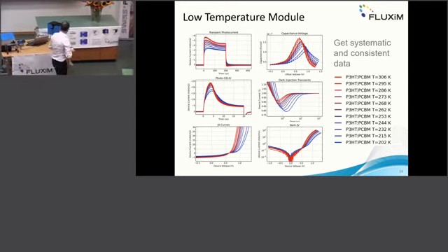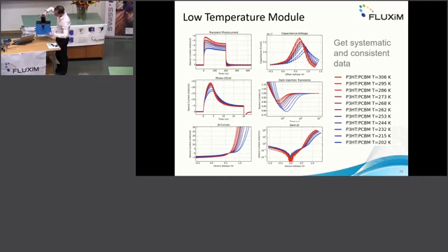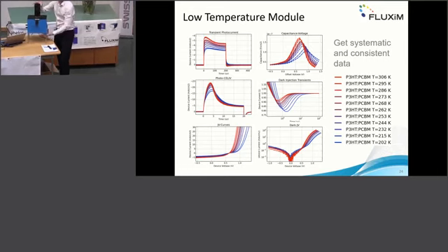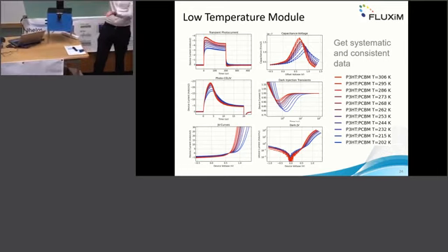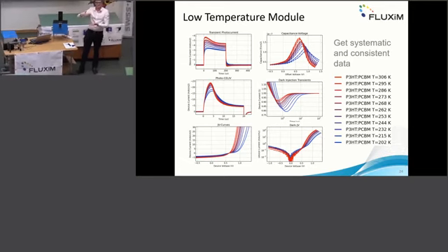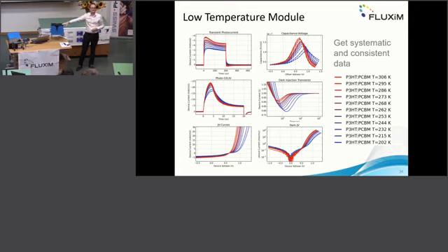We have now a new cryostat that we have here. We don't have it now running for the demonstration, but I'll quickly show you. You put your device on here, and then there's illumination from the bottom, so there's a certain distance between, and we have a light mixing rod in between because it's important. We don't want to measure the heat of the LED. We just want to measure the device, and this setup here is with Peltier element cooled, so you don't need any liquid nitrogen.